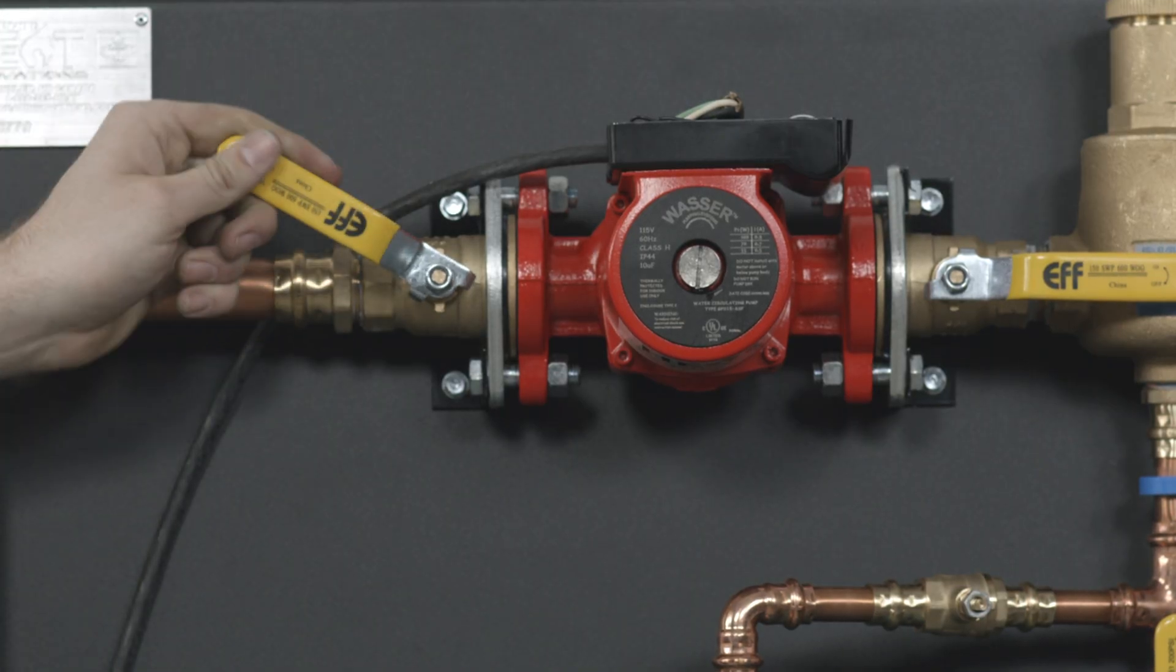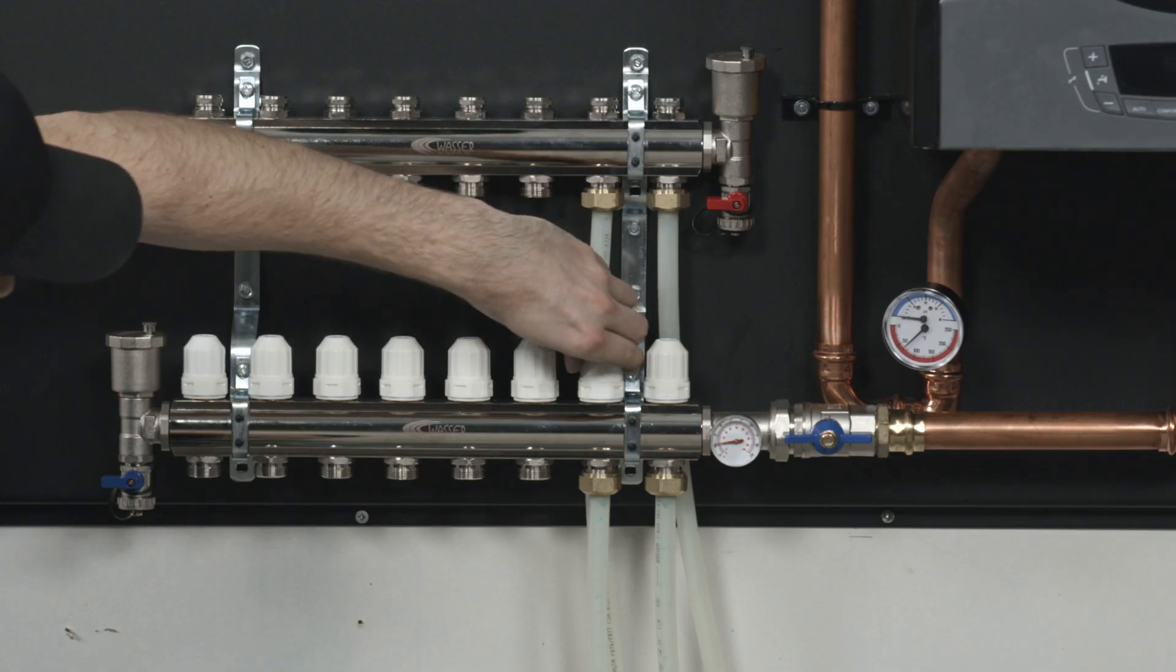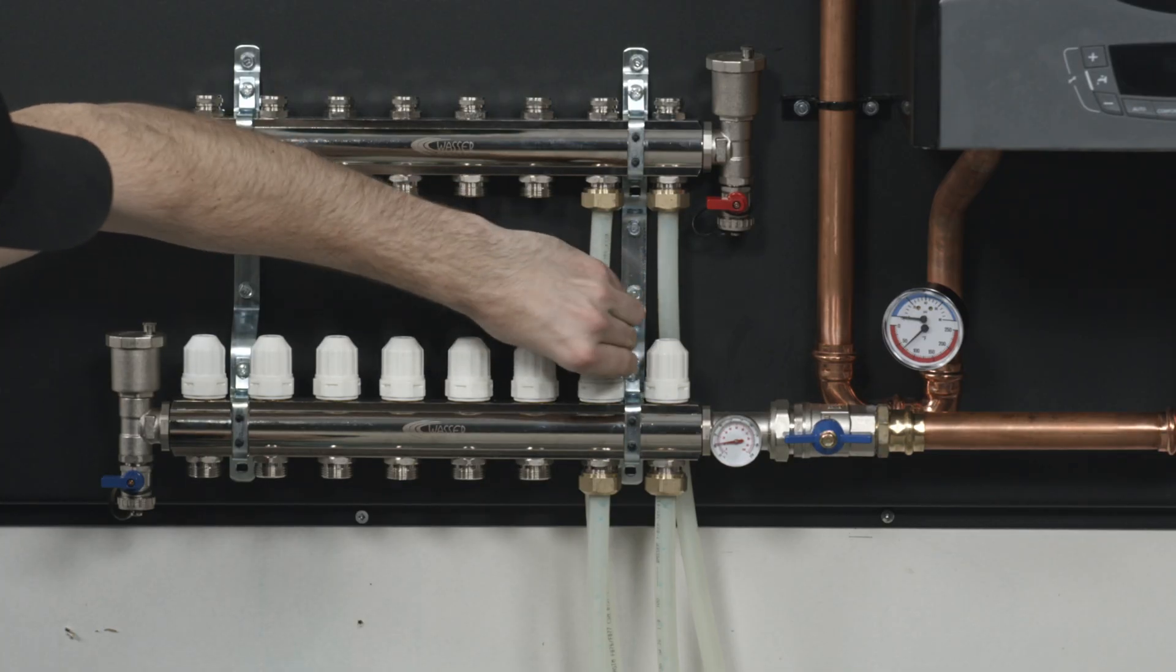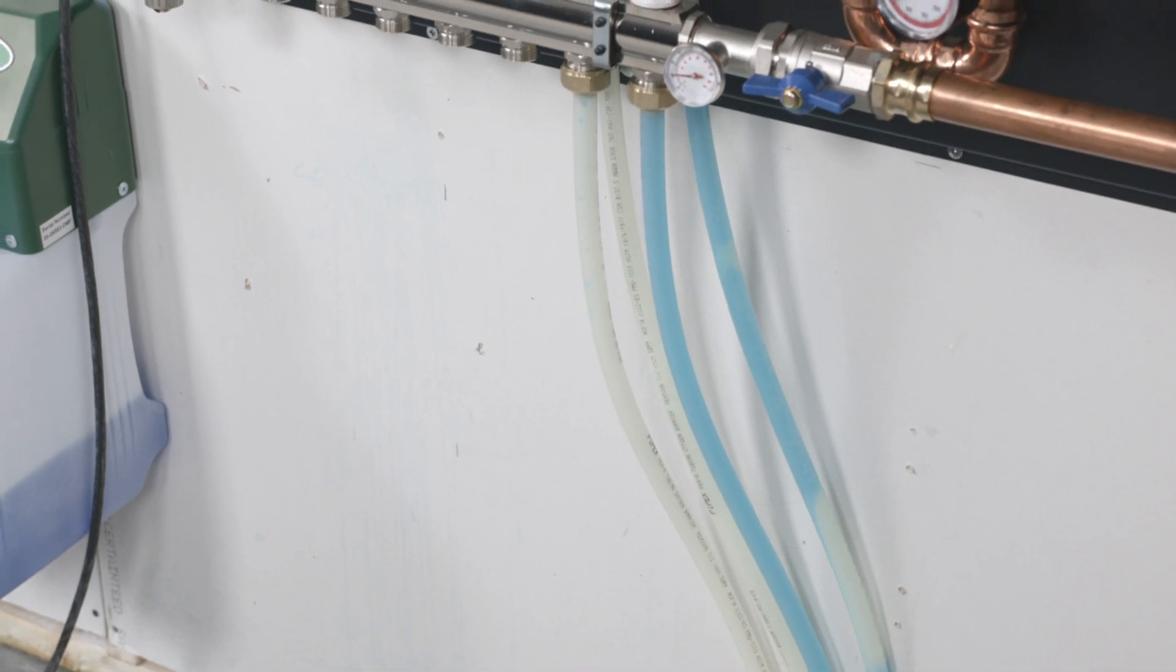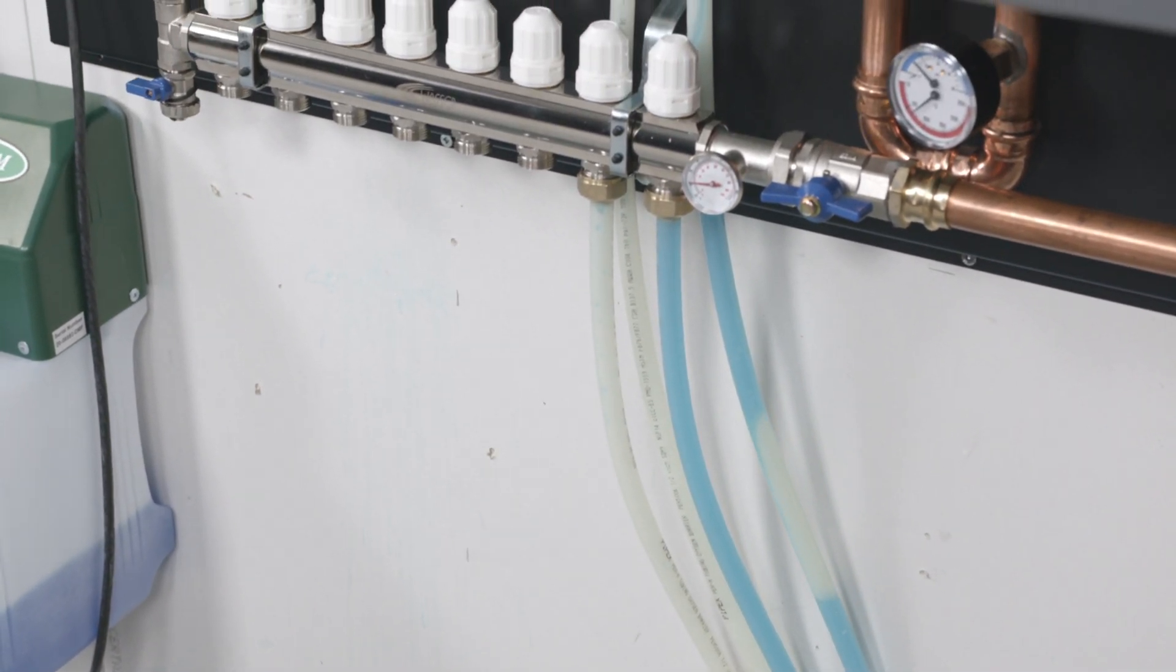Exercise the valve on the pump to assist in air removal. When the glycol feeder stops filling, open the next loop on the manifold and repeat until all circuits are purged of air and filled with water and glycol.